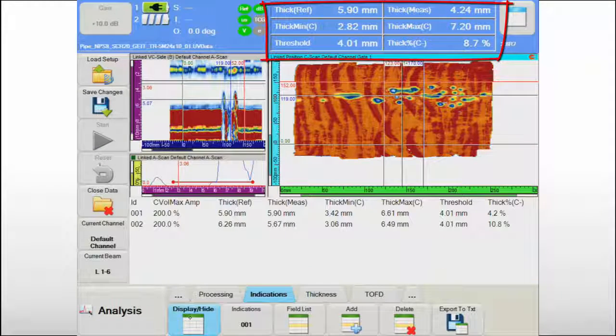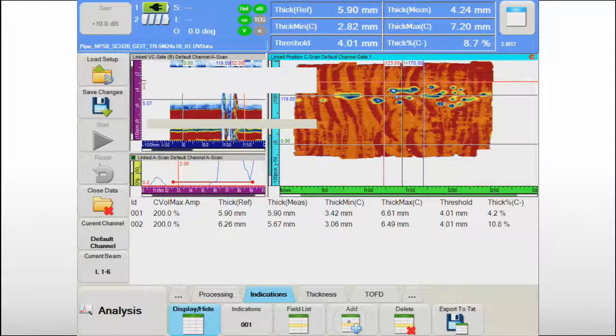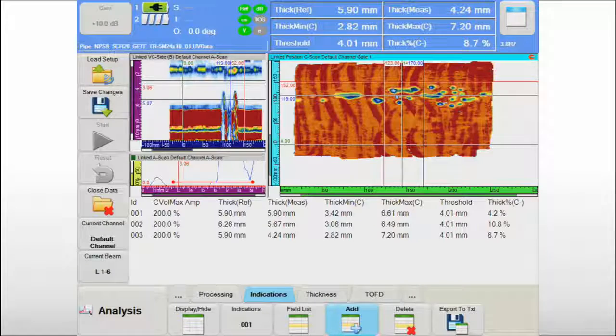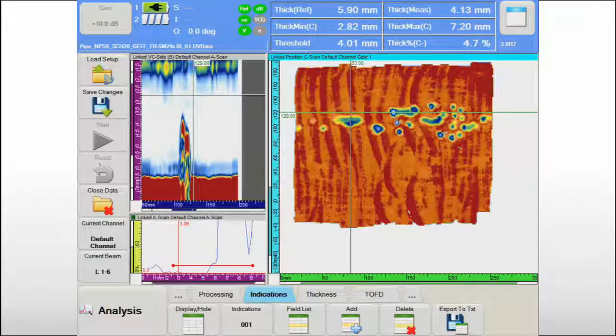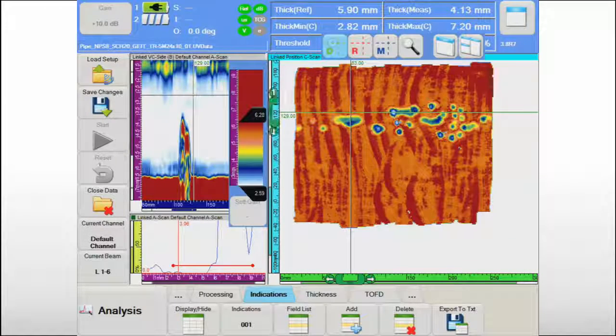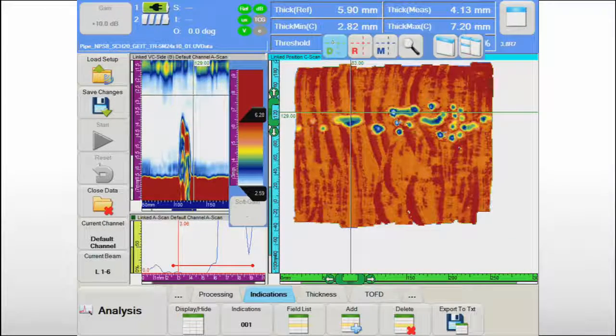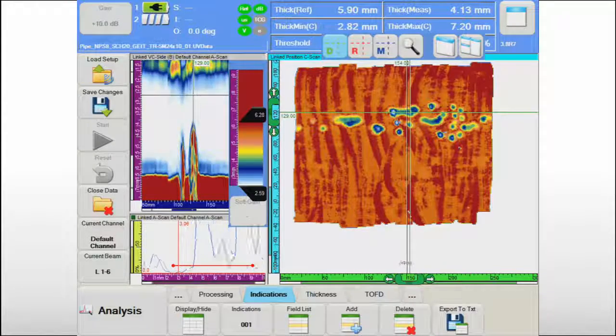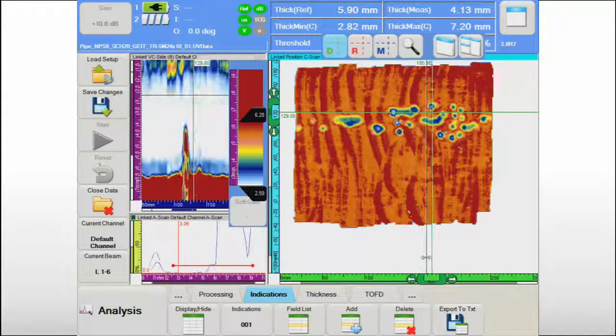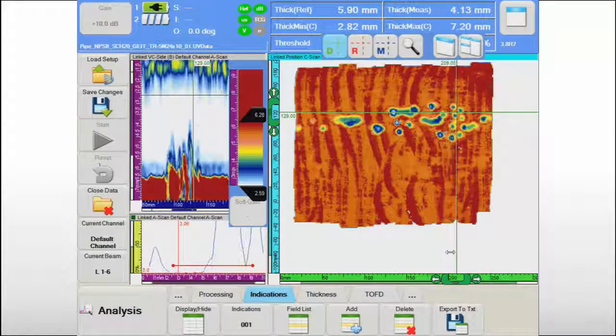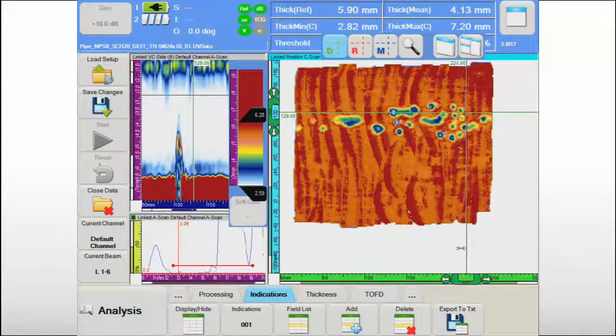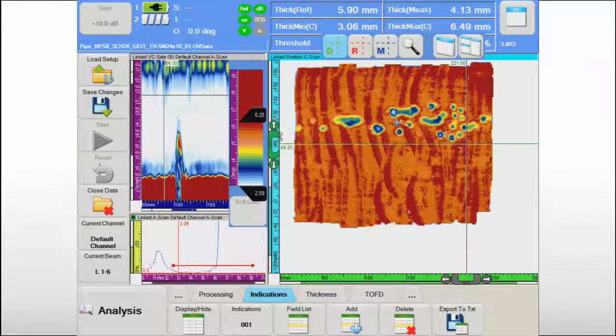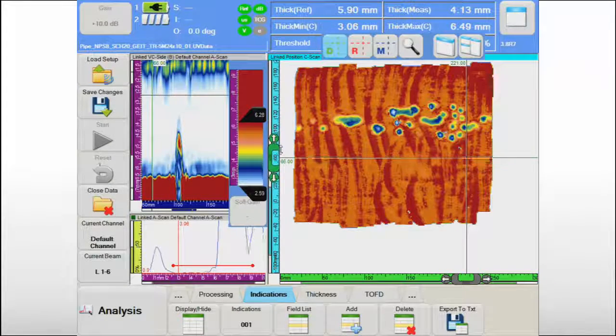The operator can also use the cursors to measure the remaining wall thickness in specific locations. As the cursors are moved in the C-scan view, the corresponding A-scan and B-scan data are automatically visualized and can be used for more detailed characterization of specific indications.